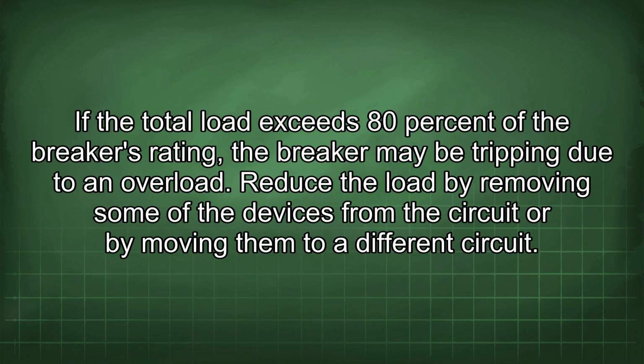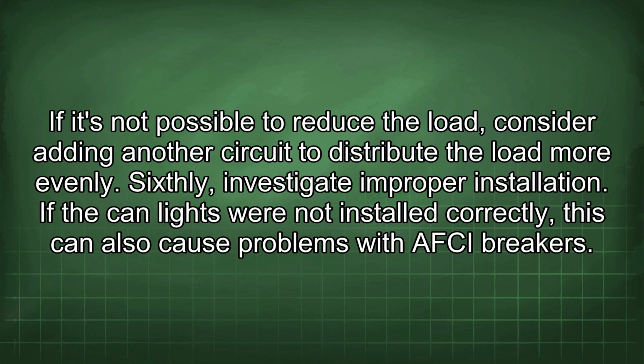If the total load exceeds 80% of the breaker's rating, the breaker may be tripping due to an overload. Reduce the load by removing some of the devices from the circuit or by moving them to a different circuit. If it's not possible to reduce the load, consider adding another circuit to distribute the load more evenly. Sixthly, investigate improper installation. If the can lights were not installed correctly, this can also cause problems with AFCI breakers.